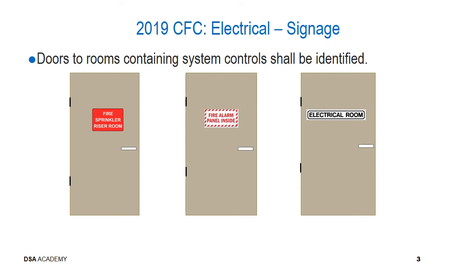CBC Section 902.1.2 and corresponding Fire Code Sections 509.1 and 604.3.1 require equipment room identification. Rooms containing fire protection equipment shall be identified in an approved manner. Rooms containing controls for air conditioning systems, sprinkler riser and control valves, or other fire detection, suppression, or control elements shall be identified for the use of the fire department.